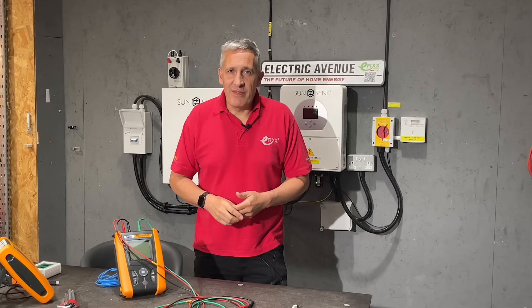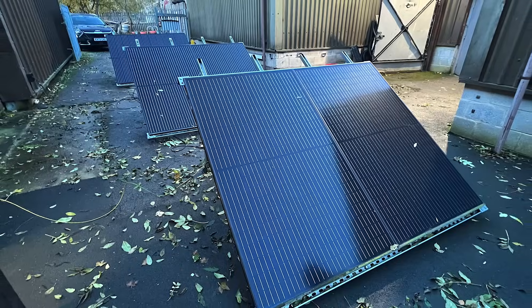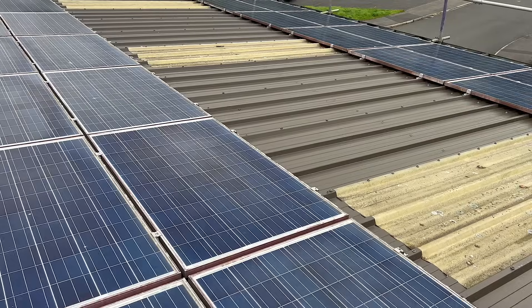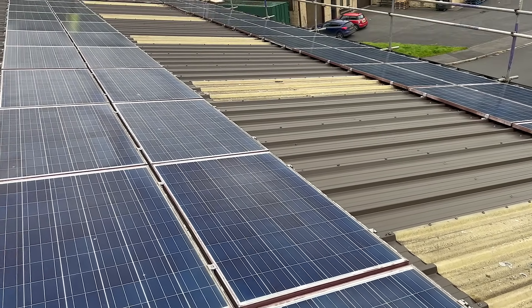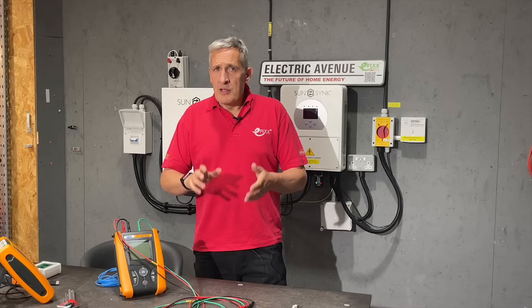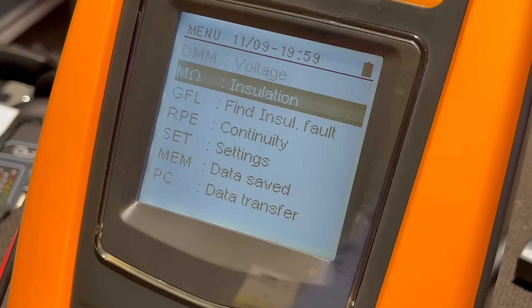The challenge now is to find where on our installation the fault is located. We've got a simple installation, but imagine if this was one of those larger rooftop installations — this could be a major mission. Here's where the really clever function in this tester steps in. Let's flip over to the ground fault locator or GFL setting. I'm led to believe ground is what the Americans call earth, so in the spirit of friendship we'll stick with that while we perform our earth fault location test.